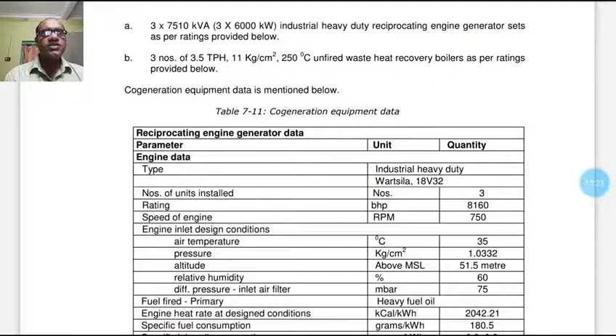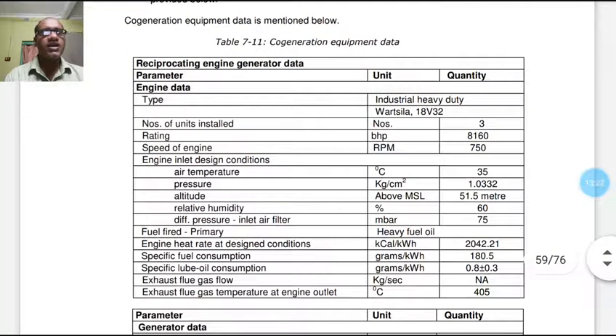So this is the reciprocating engine data. The industrial heavy duty engine is made by Wärtsilä, the 18V32, a V type engine. Number installed is 3. Brake horsepower is 8160. Engine speed is 750 RPM. Engine inlet design conditions: air temperature at normal atmospheric pressure, altitude 51.5 meters, relative humidity 60, and differential pressure across the inlet air filter is 75 millibar.